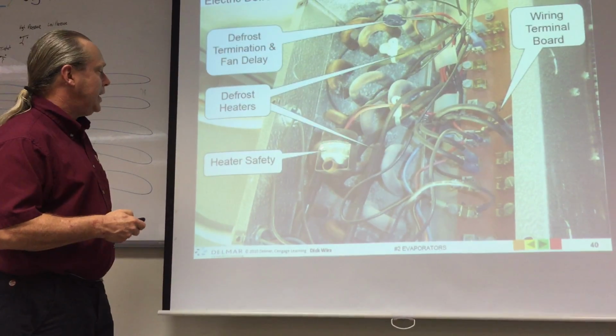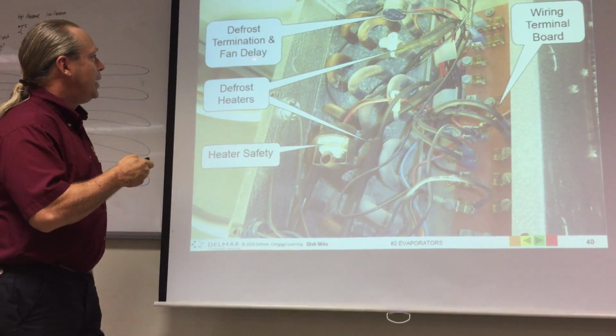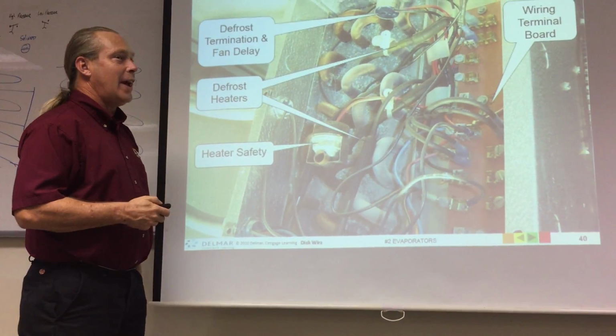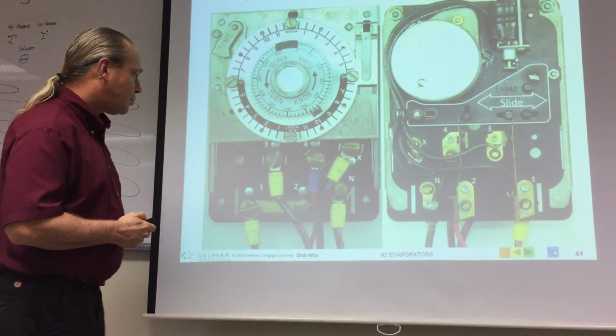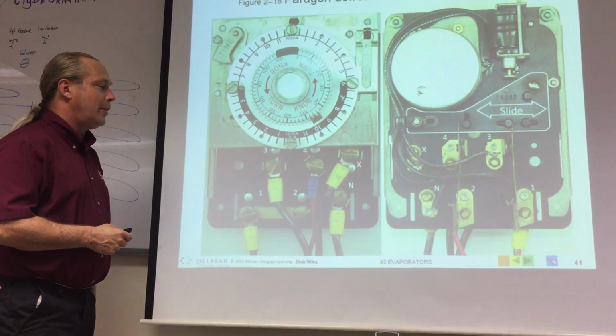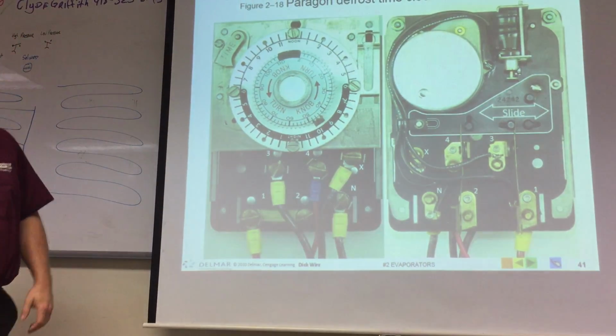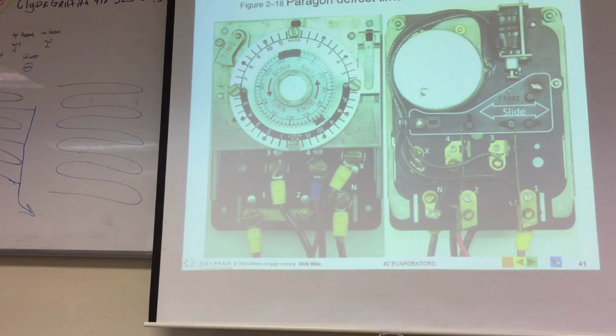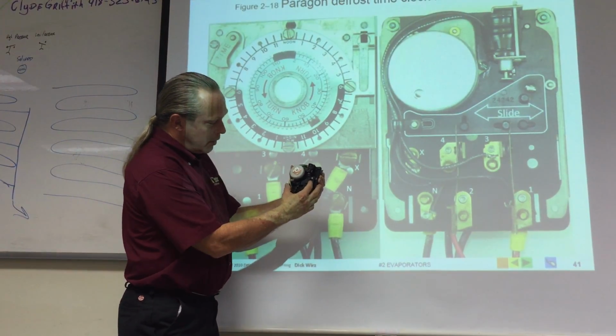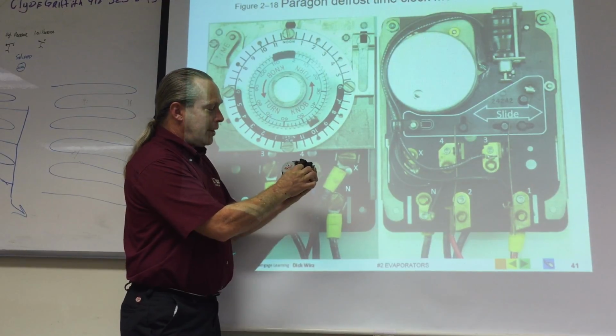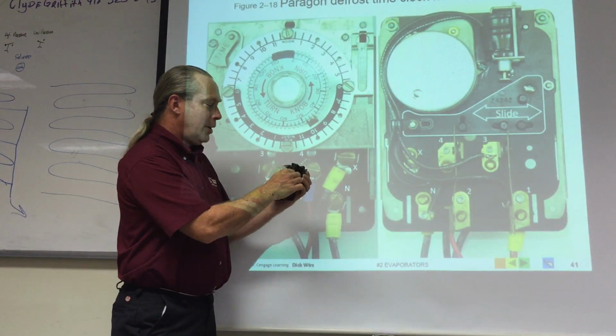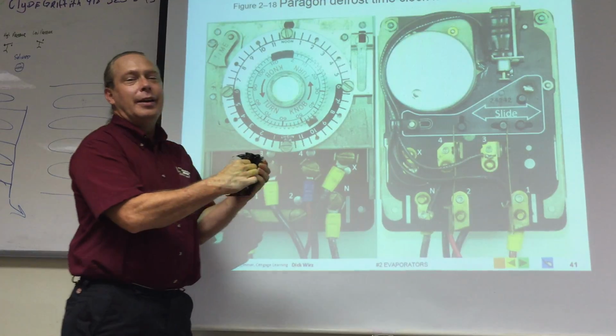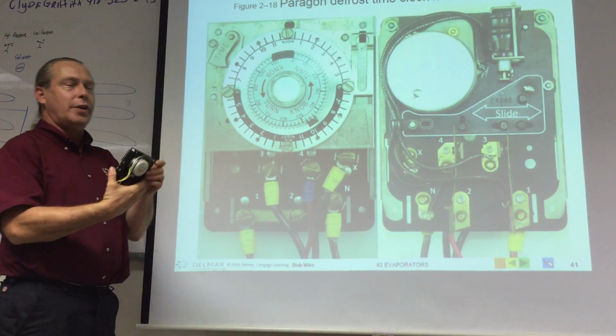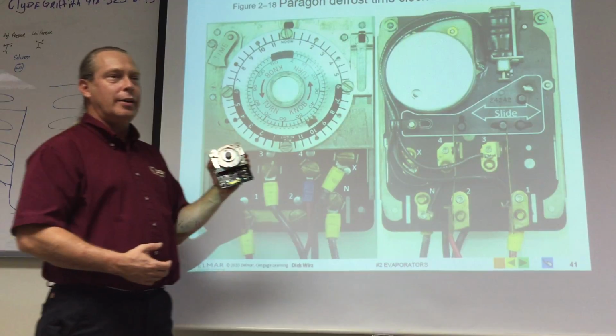So here's our defrost heaters and our heater safety and our defrost termination and fan delay. And here's our defrost timer that's completely connected. What they want to show you in this is that there's a slide right here. And this little solenoid that's all kinds of burn up with this one could activate this slide and take it out of defrost even though the time clock wasn't ready.